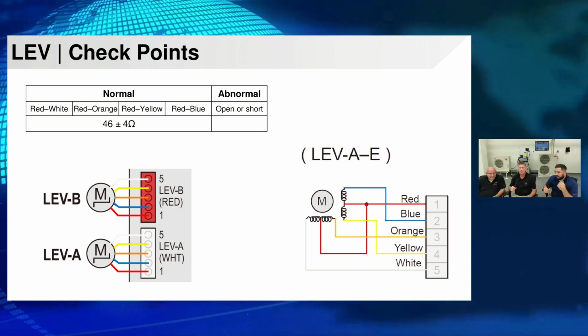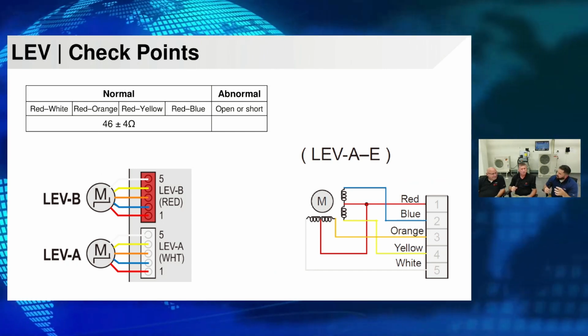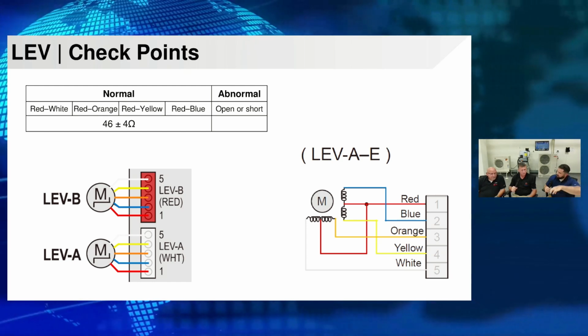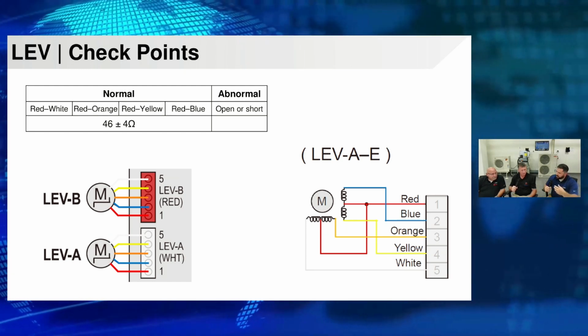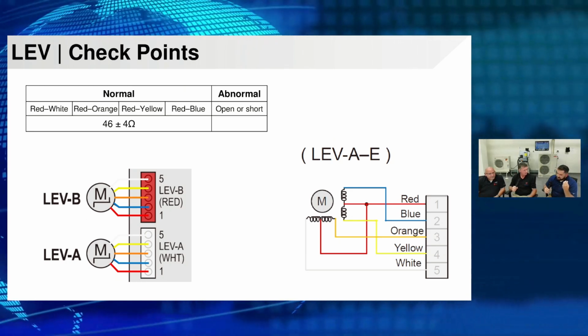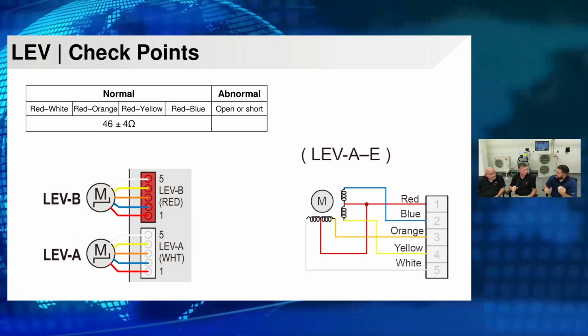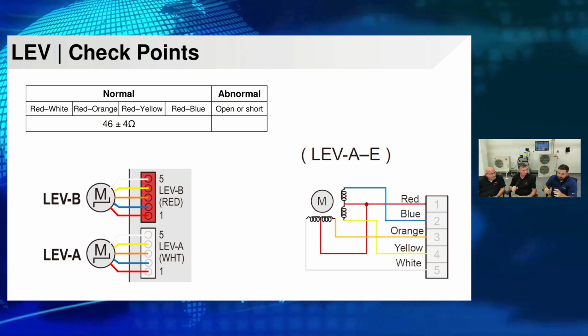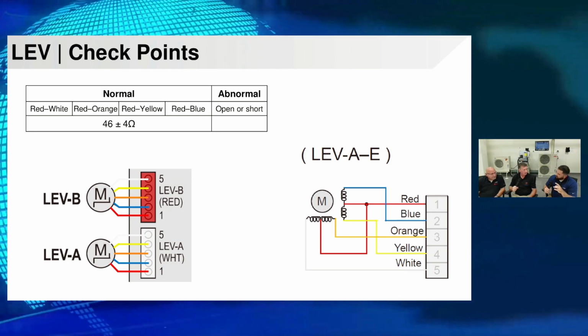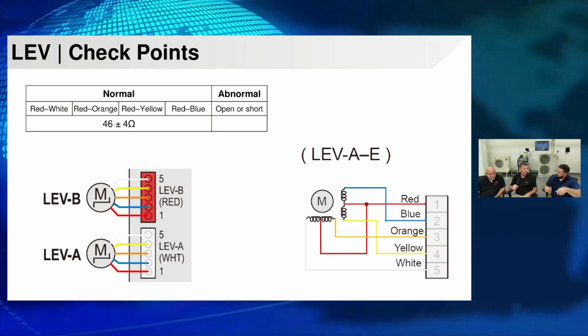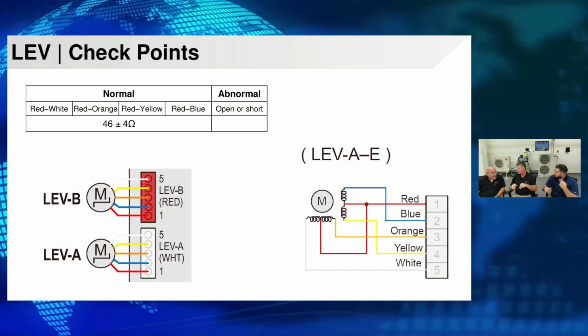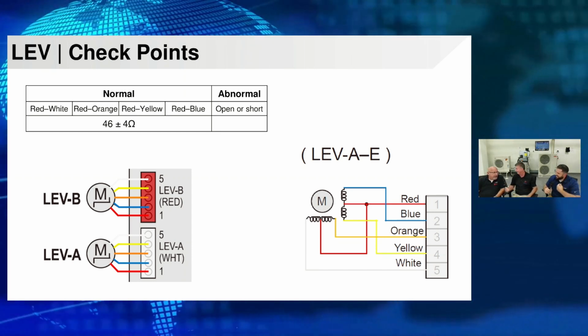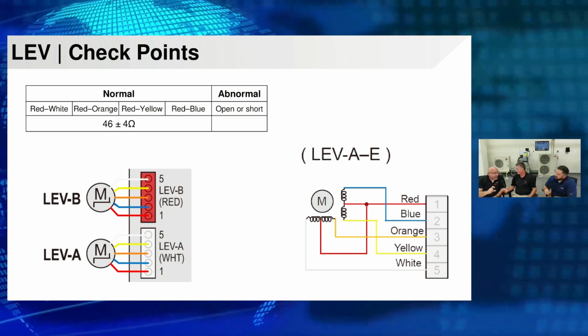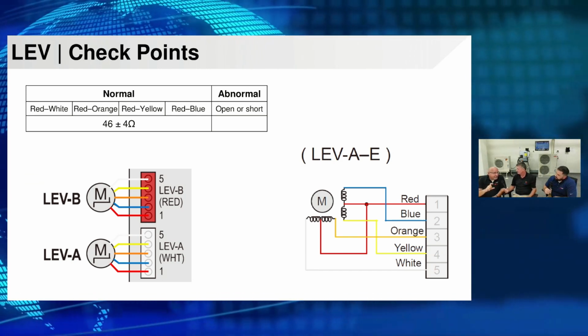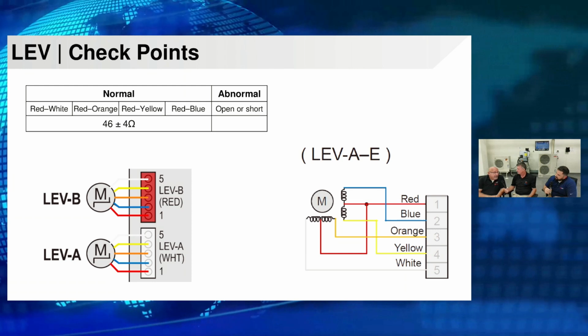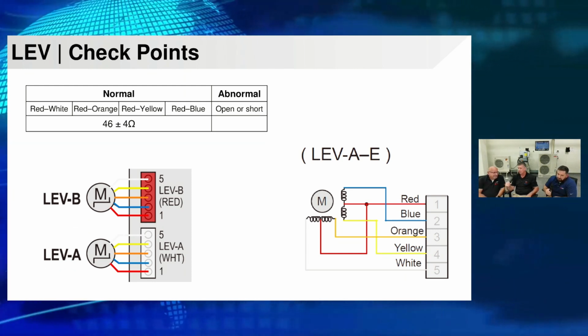Wow. So we've got 2 components. You actually have your solenoid, which is what's making that magnetic field in order to open and close. And then we have the body itself. So if we have a suspicion that we have a failed mechanical side of that LEV, we have these donut magnets, is what we call them. And that will allow you to manually try to drive that LEV open and close. That's a lot of spinning on a 6,000. Yeah. Do that because you don't know where it's at. And if you're not testing temperature, you could over open it and flood the compressor. Absolutely. You always talk about superheat.